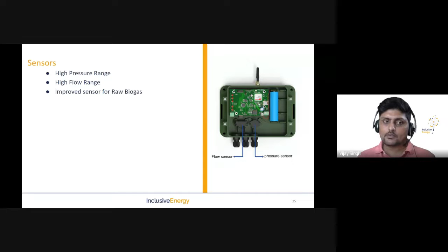We have also improved our sensor technology. Earlier we had an issue where the sensors were failing due to high humidity and H2S content, but now we have improved on that. Along with that, we have improved our range on pressure and flow measurement - now we have a product ready to measure up to 20 meter cube and 5 bar. The 5 bar version is going to be launched very soon.